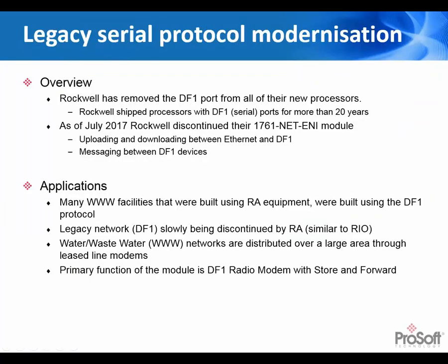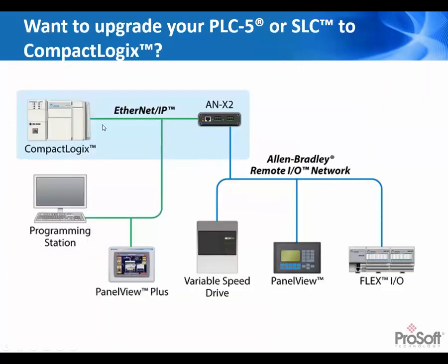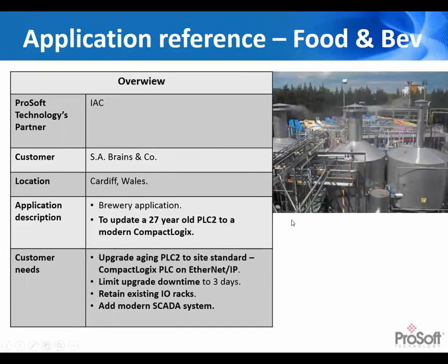Any other questions before I move on? In this scenario, you can control the existing remote I/O network over the Ethernet IP network, but the customer in the other case wanted to retain the existing I/O rack, so that's why they needed the ASB module.